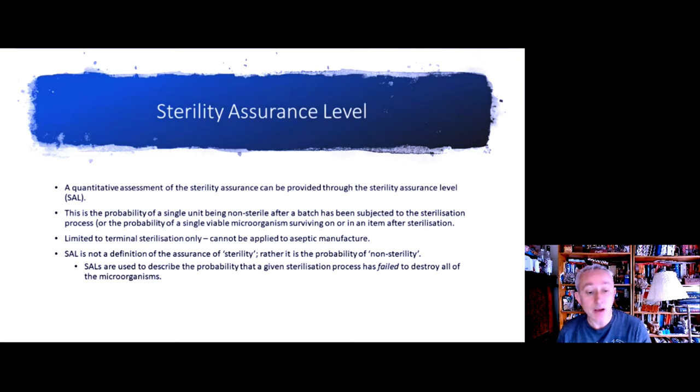So what do we mean by the sterility assurance level? Well, the sterility assurance level is a quantitative assessment of sterility and it describes the probability of a single unit being non-sterile after a batch of product has been subject to a terminal sterilization process. Or in other words, it's about the probability of a single viable microorganism surviving on or within an item after it's been sterilized. This term is limited to terminal sterilization, so it cannot and should not be applied to aseptic manufacturing.